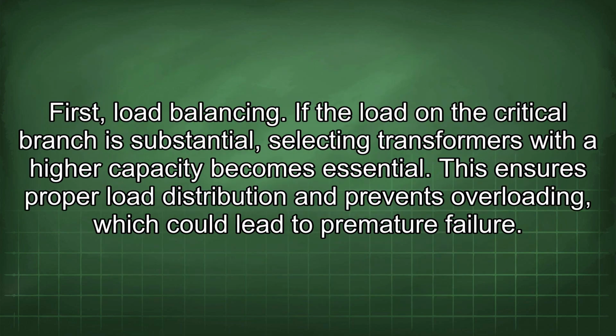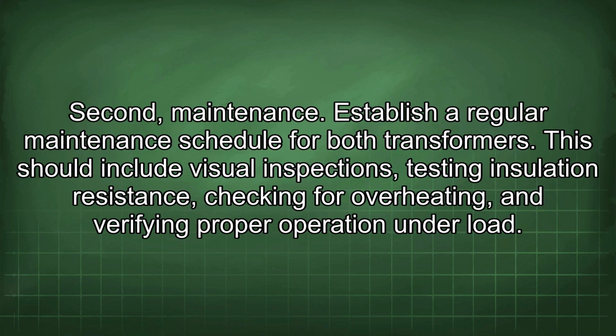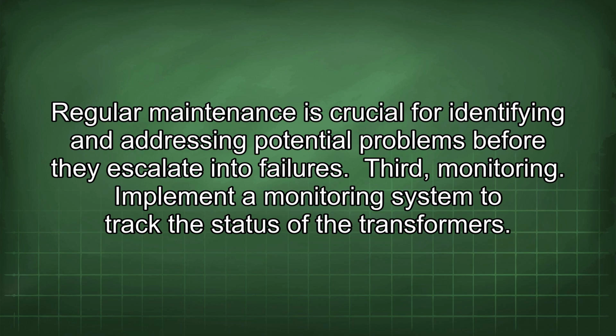First, load balancing. If the load on the critical branch is substantial, selecting transformers with a higher capacity becomes essential. This ensures proper load distribution and prevents overloading, which could lead to premature failure. Second, maintenance. Establish a regular maintenance schedule for both transformers. This should include visual inspections, testing insulation resistance, checking for overheating, and verifying proper operation under load. Regular maintenance is crucial for identifying and addressing potential problems before they escalate into failures.